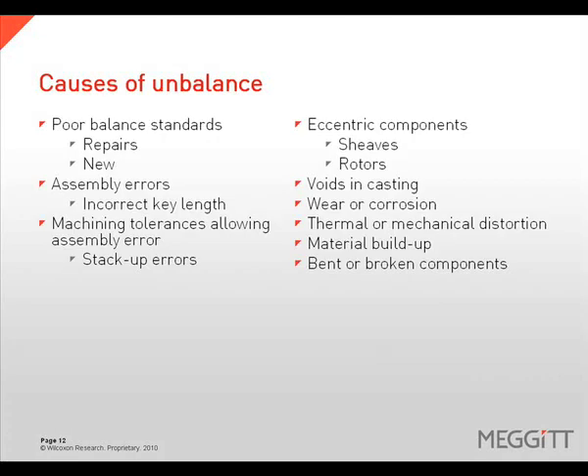There are many causes of unbalance: poor balancing standards for repairs or new equipment, assembly errors such as the wrong shaft key length, machining tolerances stack-up error, eccentric components, wear or corrosion, and material build-up, just to name a few.